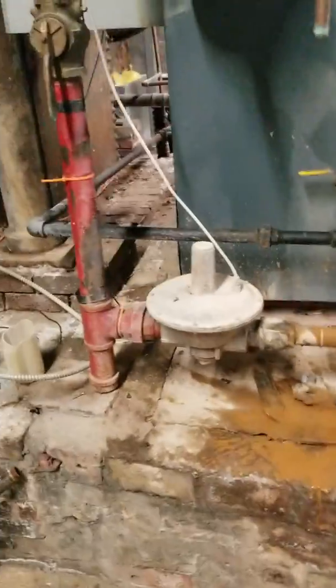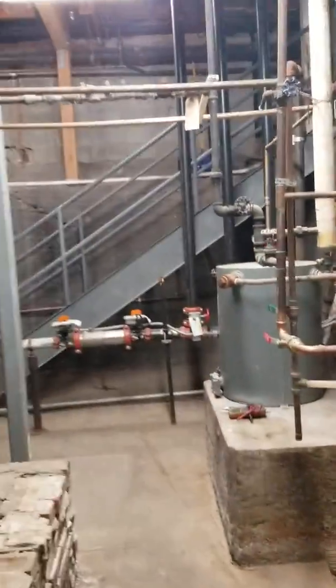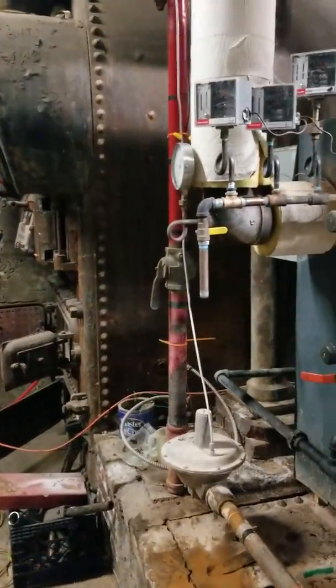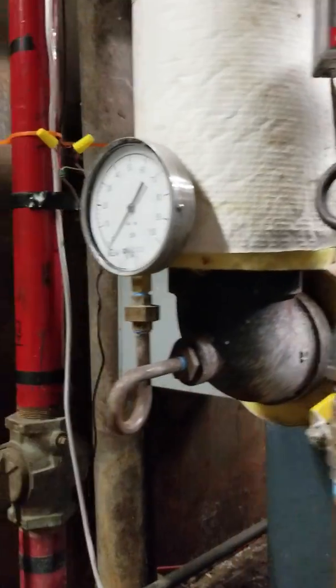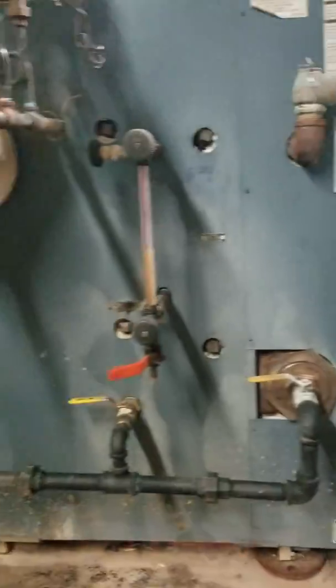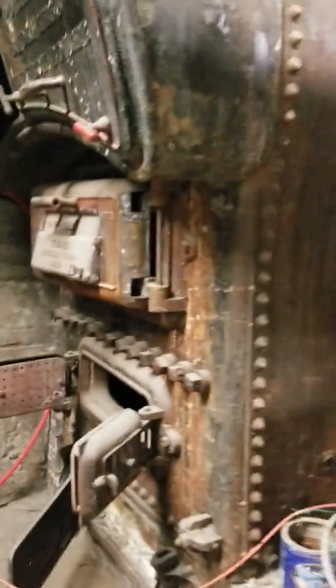The single pipe system is very rare anymore. But up in the building itself, you have to keep all of the valves open on all of the radiators. It runs at a very low pressure — two, three, four pounds; five pounds is max. And that's so the water can come back. Water weighs 8.33 pounds a gallon, clean water. But crazy cool.